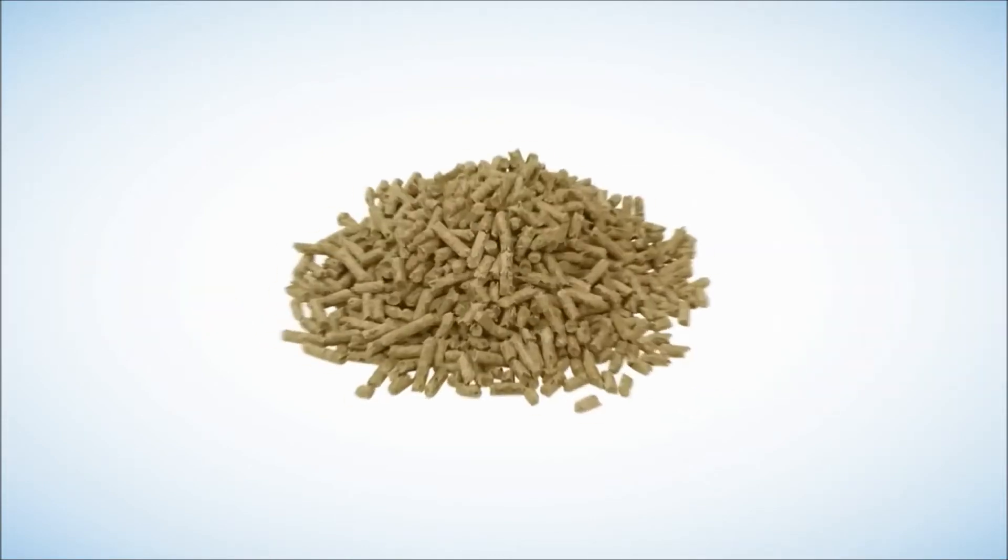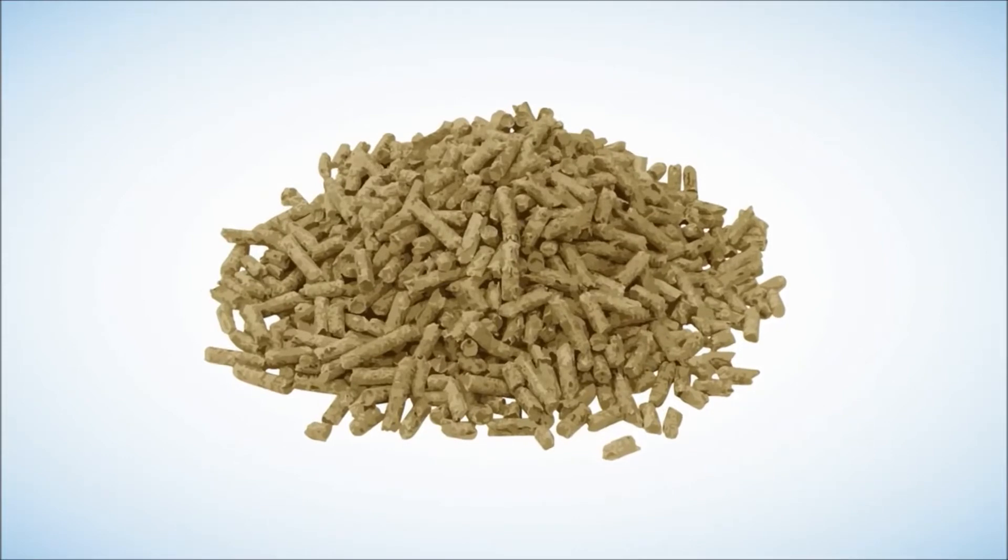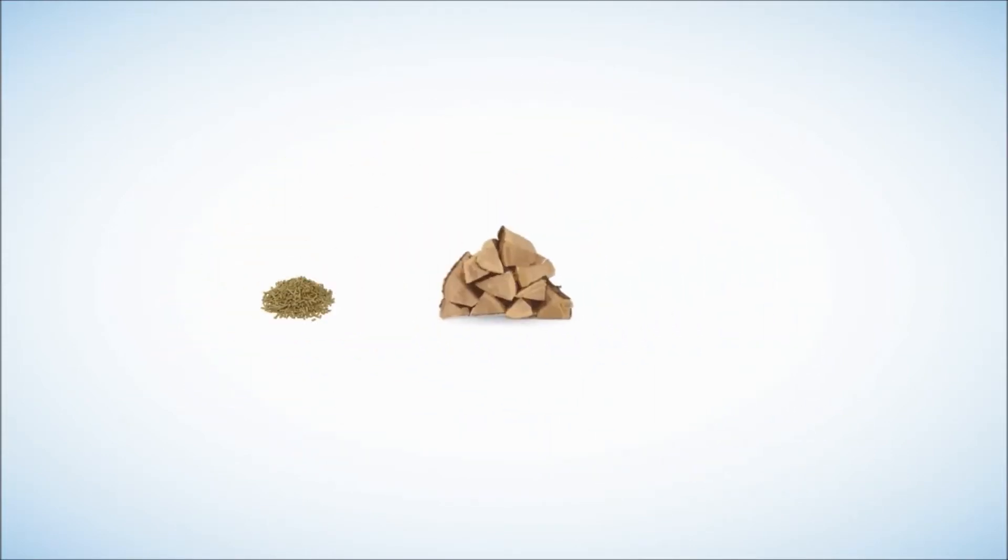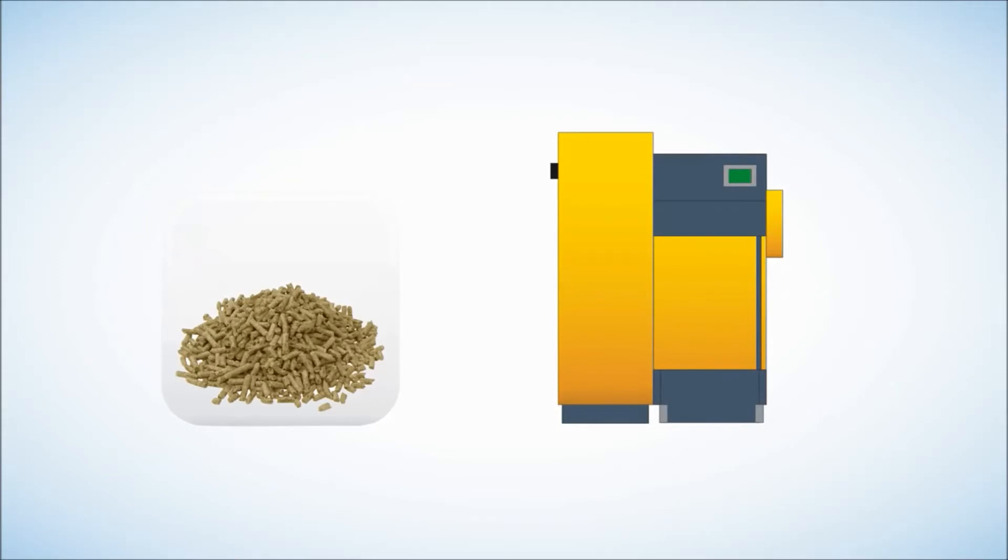Wood pellets are generally manufactured from byproducts from sawmills and other wood processing industries. They need less storage than logs or chips as they have a higher calorific value for the same volume. Wood pellet boilers are generally fully automated with the pellet sucked by vacuum straight into the boiler from the store, so are easier to run than log boilers.